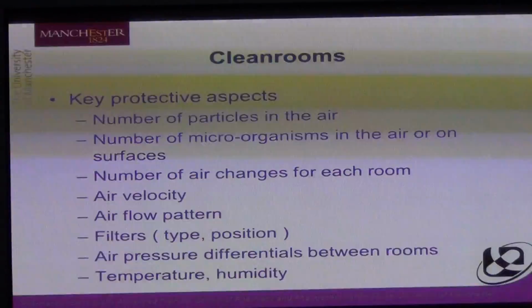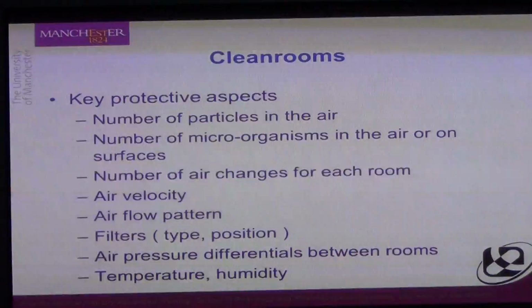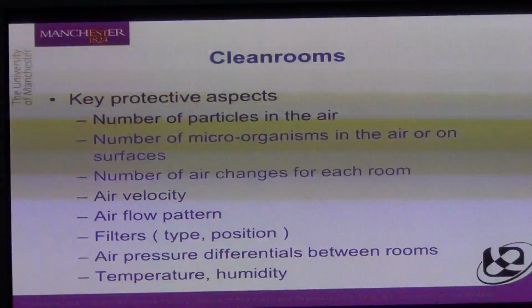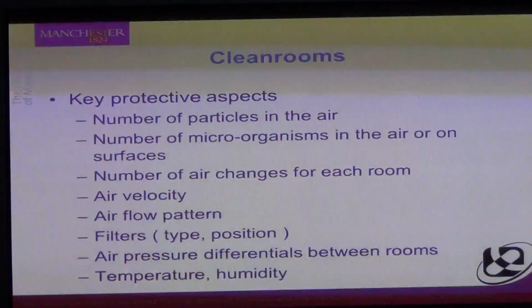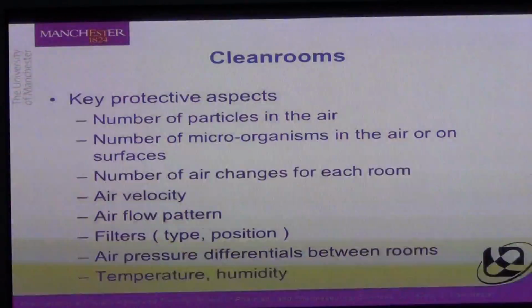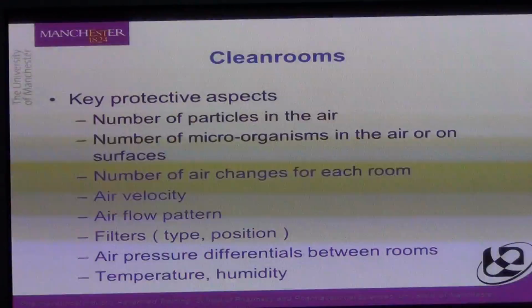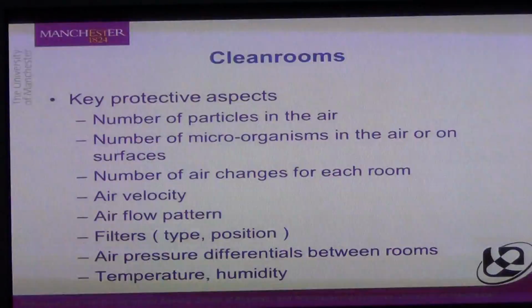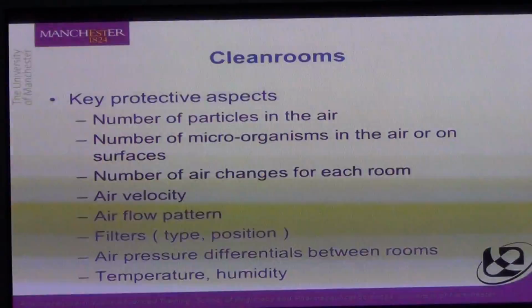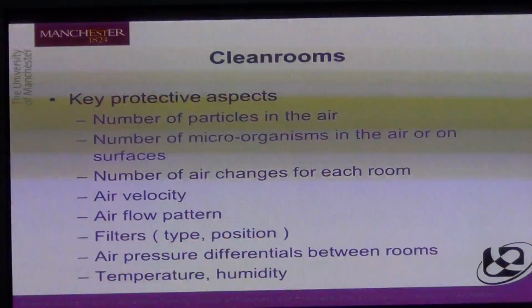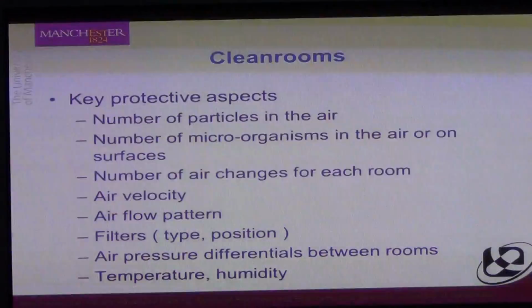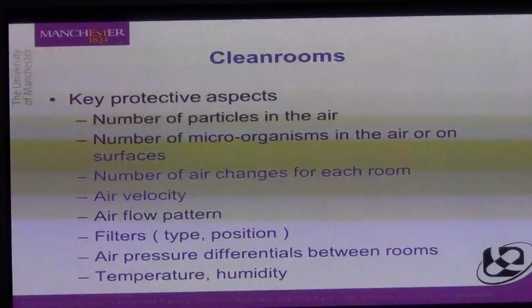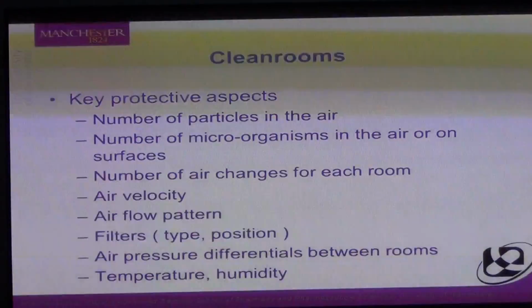For unidirectional airflow devices, we have air velocity. That's the speed that the air gets pumped into the laminar airflow cabinet, and it's designed to sweep away contamination. We also have to look at airflow patterns, with smoke studies around that. We also have the filtering of the air, I mentioned the HEPA filters earlier. We also have pressure differentials between clean rooms of different grades. This means that the cleaner clean room is at a higher pressure than the clean room of a lower grade, so the air blows out and the air cannot blow in. And for aseptic filling, we have requirements for temperature and humidity, and that's mainly designed for operator comfort and to stop the operators from perspiring too much.